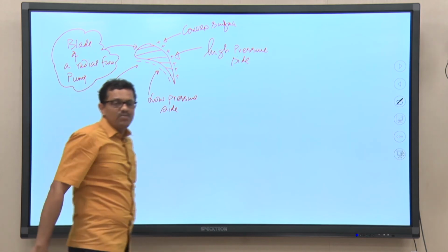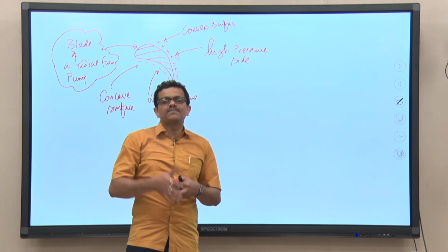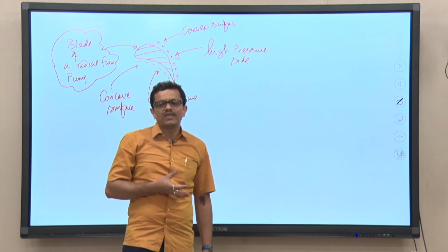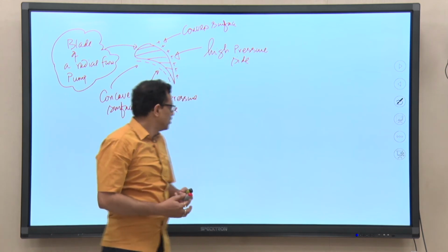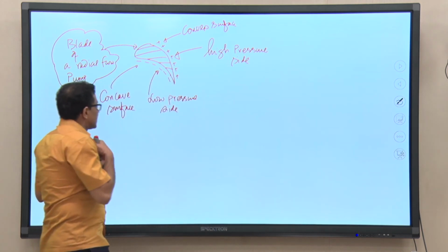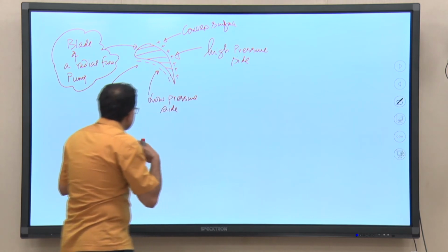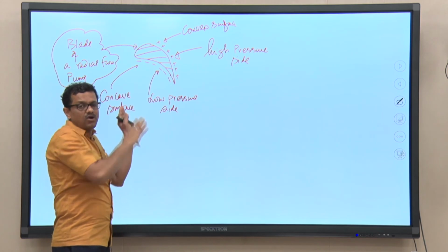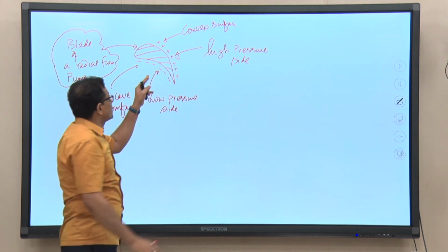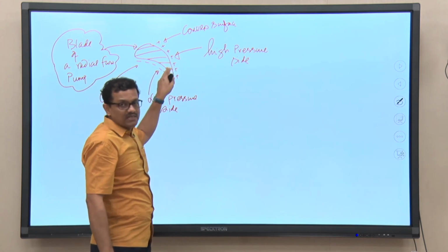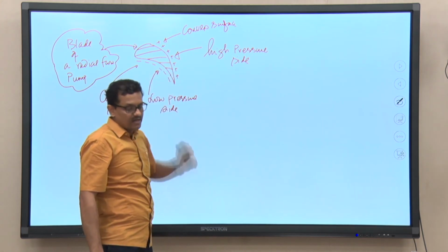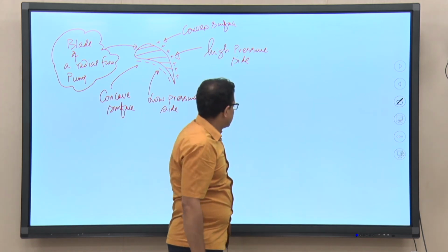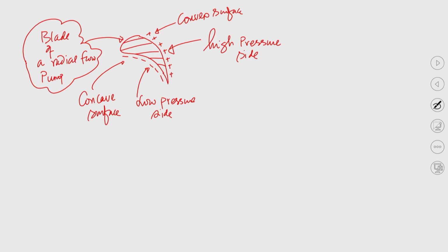Again there will be a force, and perhaps because of this force the effect of slip will come into the picture, and that is what we are supposed to discuss. Okay. Now, you can see this is the only difference between the blade of a radial flow pump and the isolated airfoil. For the isolated airfoil, the convex surface pressure is less, but for the pump blade it is high, fine.